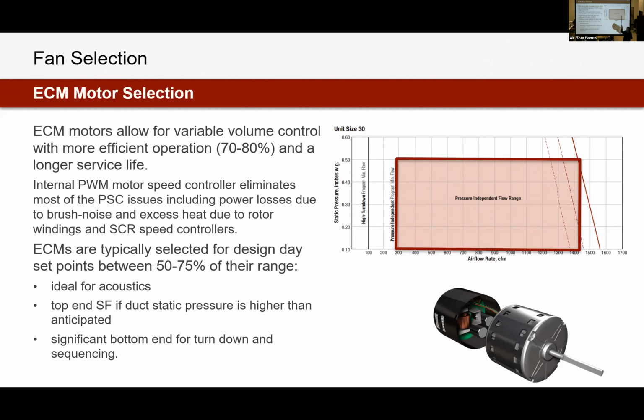So if I'm at 1200 CFM, it doesn't matter if my static pressure changes from 1/4 of an inch all the way up to 1/2 inch. The motor's going to compensate and hold that airflow. Again, for my engineering students, PID loops. Ring a bell, maybe? Using a PID loop to compensate for the change in pressure and then change our airflow. So up to 1/2 inch, we're gonna hold that same airflow. A really good practical application for this, imagine if you have a filter on the box. Over time, the filter is gonna be loading. That filter pressure drop is gonna change, it's gonna be variable.